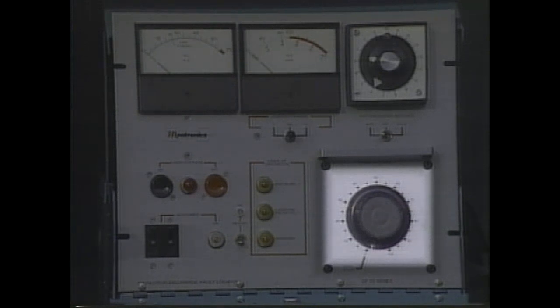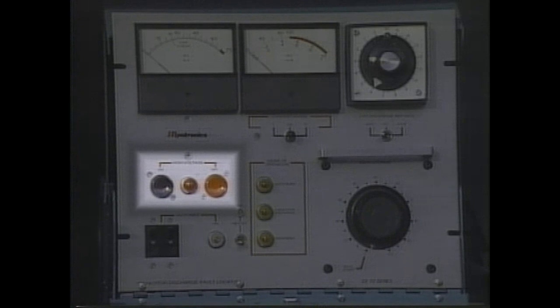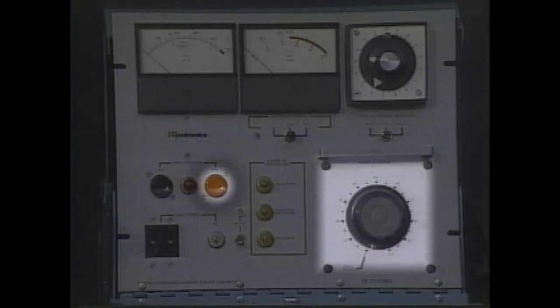We can adjust the amount of current we use in the burn mode, or we can adjust the voltage output in the thump mode with the large black knob just below the timer on the left side. Just below the voltmeter, there is a black and red push button switch. These are the high voltage on and the high voltage off switch. The high voltage off switch should never be used until the large black control knob has been reduced to 0.